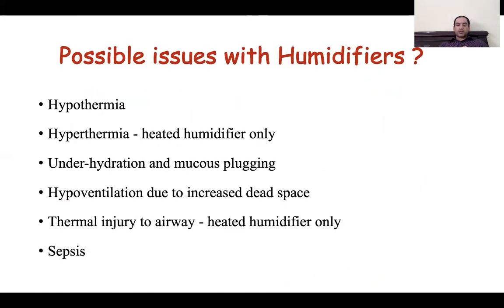There are certain possible issues which can happen with humidifiers. If the temperature — especially in manual humidifiers — is not set appropriately or there is malfunctioning of the humidifier, it can lead to both hyperthermia and hypothermia. There can be under-hydration and mucous plugging if humidification is not adequate. There can be increase in dead space leading to hypoventilation, and there can be thermal injuries and sepsis. Because of rain-out, the condensate can get contaminated with microorganisms and the same condensate can then go into the respiratory system, causing pulmonary infections.